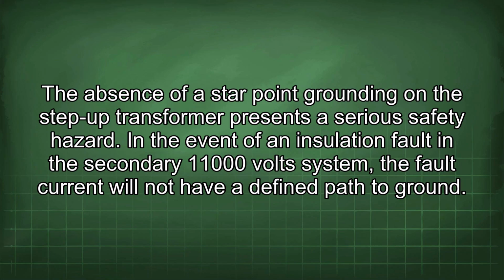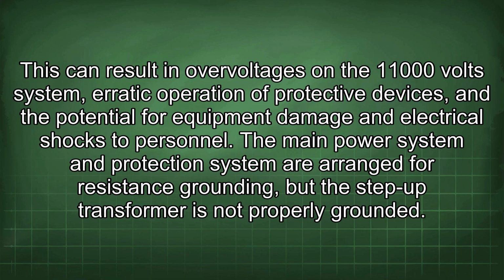The absence of a star point grounding on the step-up transformer presents a serious safety hazard. In the event of an insulation fault in the secondary 11,000-volt system, the fault current will not have a defined path to ground. This can result in overvoltages in the 11,000-volt system, erratic operation of protective devices, and the potential for equipment damage and electrical shocks to personnel.